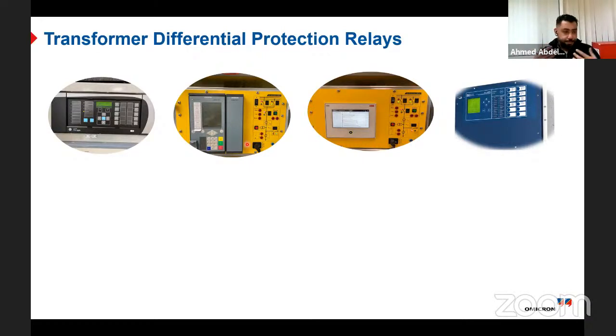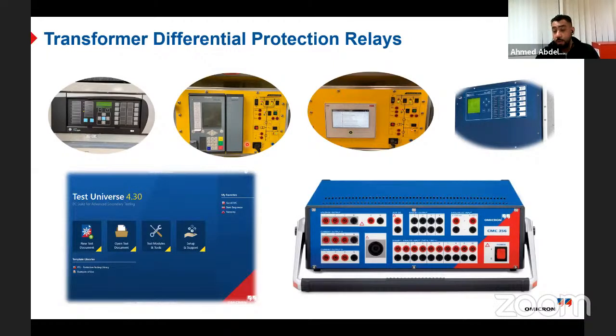With Omicron, we have a great solution to help you test this kind of protection relay. With one powerful tool, we have it. It's Test Universe, our operating software, and our CMC, our main horsepower, the CMC 356. It generates 3-phase voltage and 6-phase current, because in differential protection you need 6-phase current to simulate the high voltage side and low voltage side.